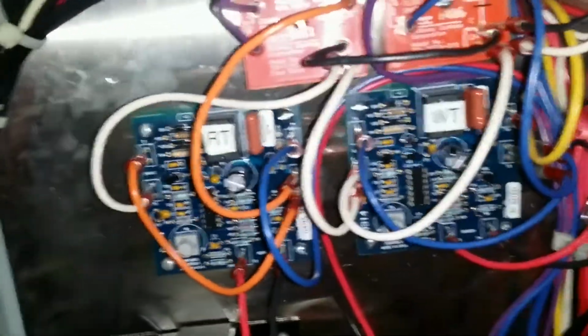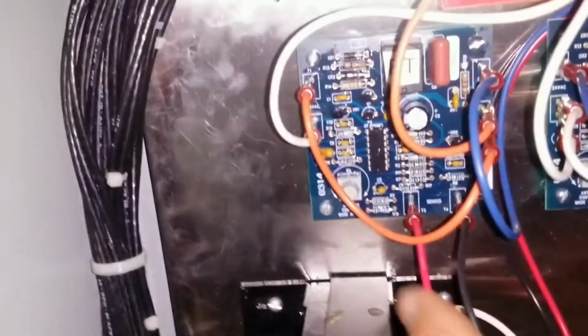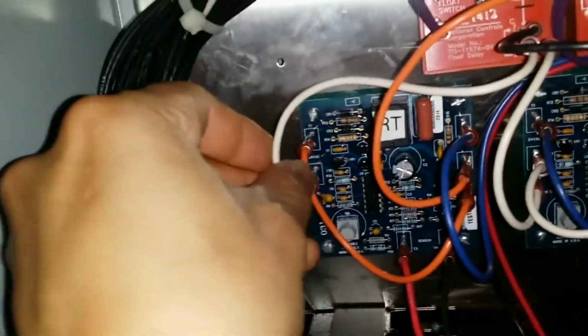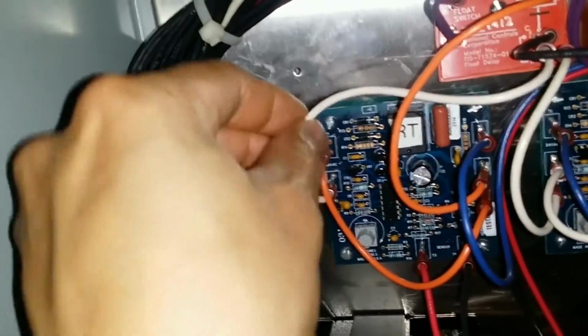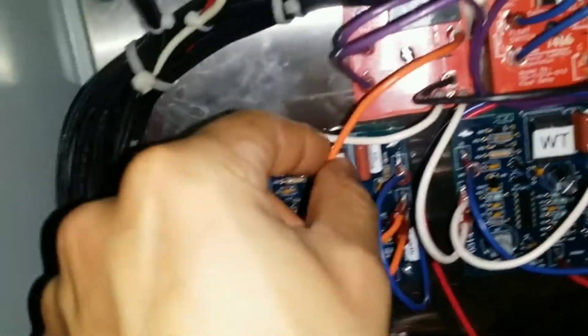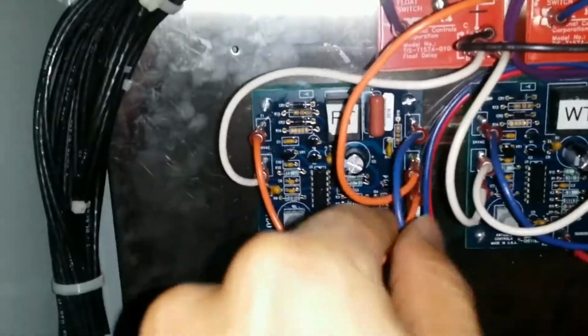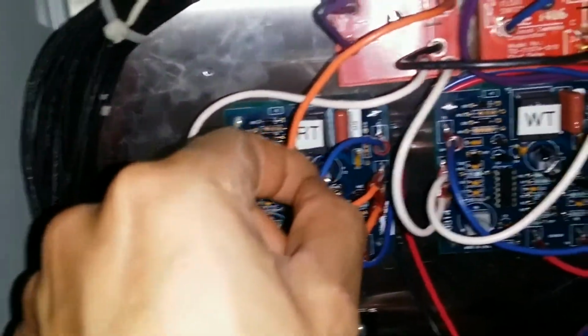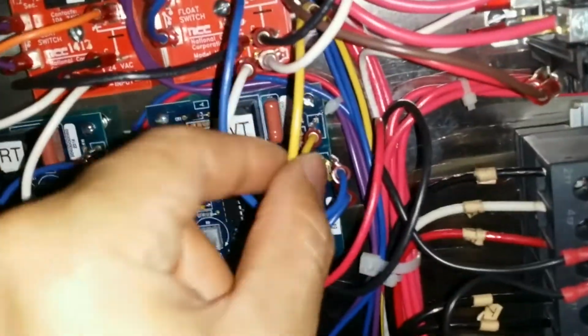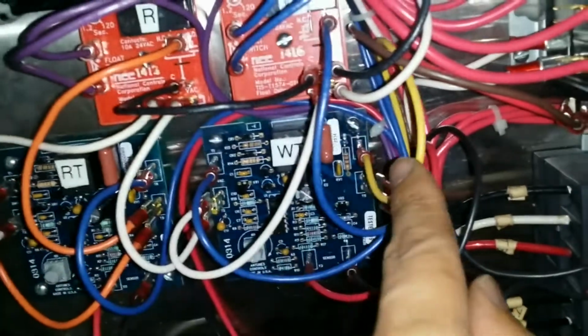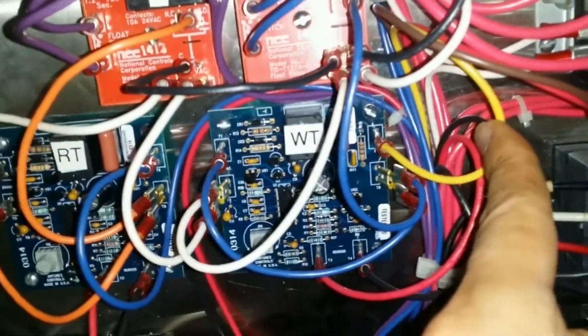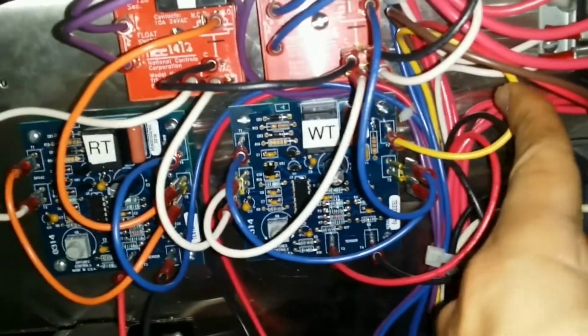These work identically as these two over here. Once again, temperature probe. This over here is powered to power the circuit card. We always got this one. This is conditional power; we will only get power over here whenever this one says that there is water. And this one goes to the rinse steam solenoid, and this yellow wire over here goes to the water solenoid for the wash tank.